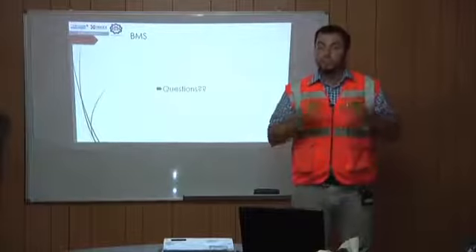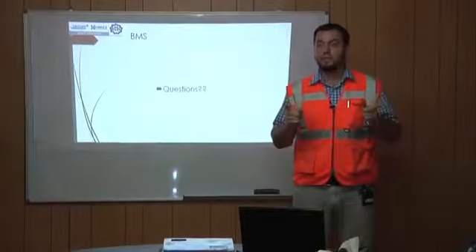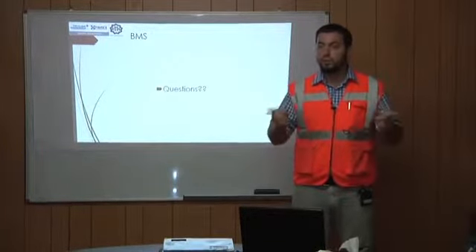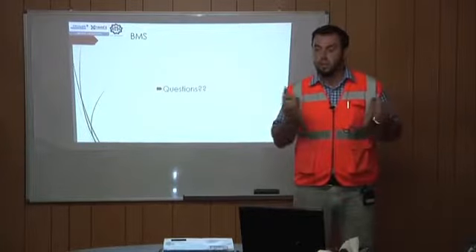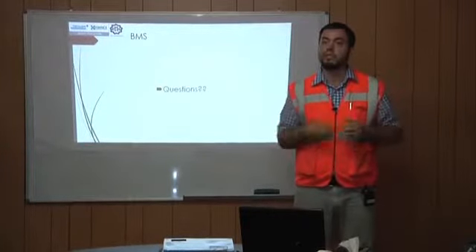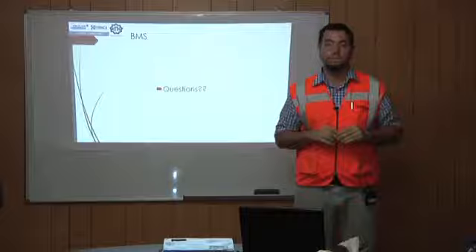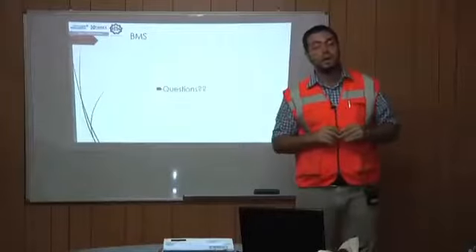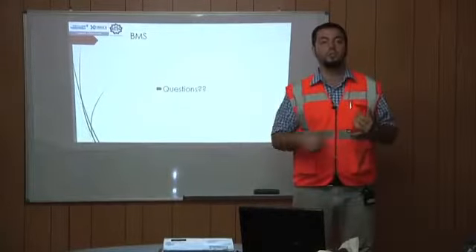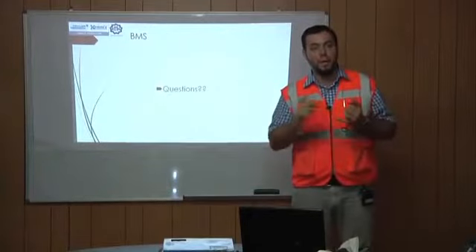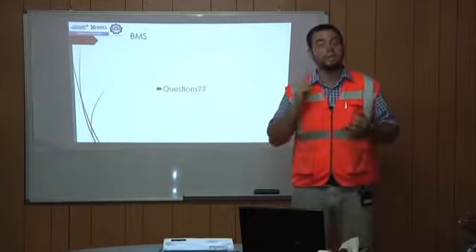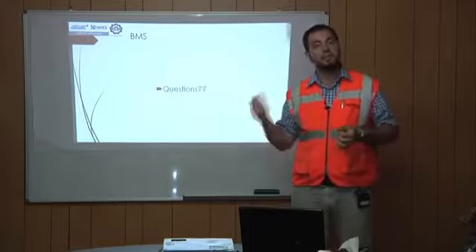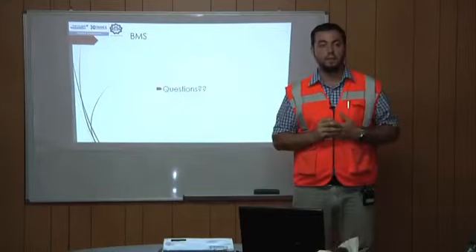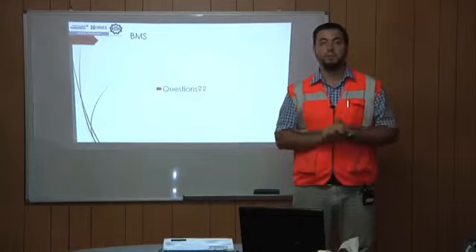For the fresh air, yes. 2 fresh air dampers on every single RTU, on the 4 RTUs, both are connected to the BMS. So you can control how much fresh air you're intaking. Fire dampers are installed in the communication rooms, and fire smoke dampers are installed in the communication rooms and the UPS room, and this is monitored by the BMS. Anything else? Perfect. Thank you very much.